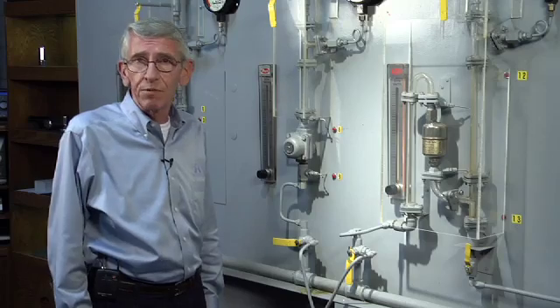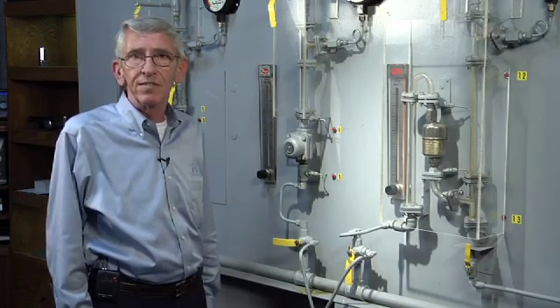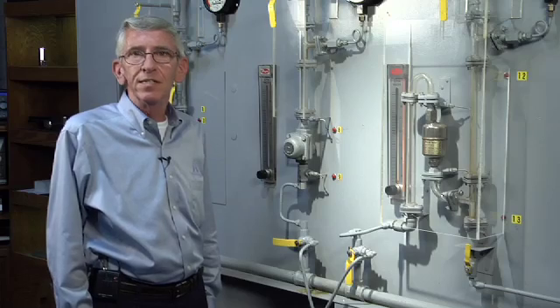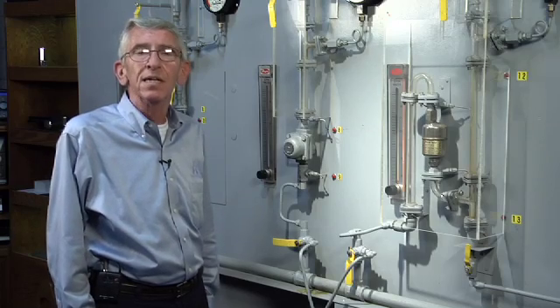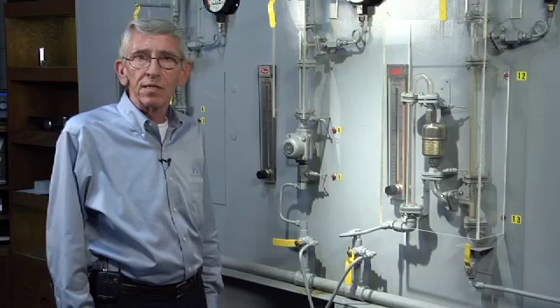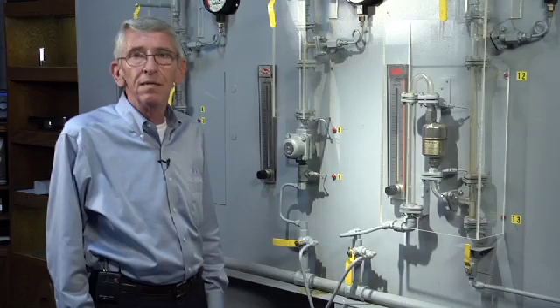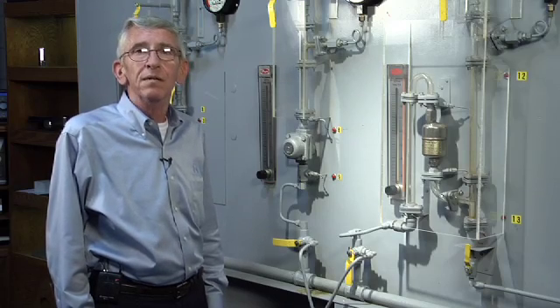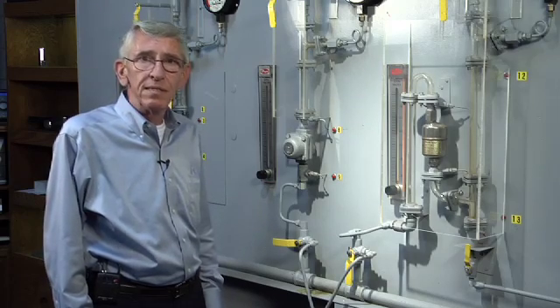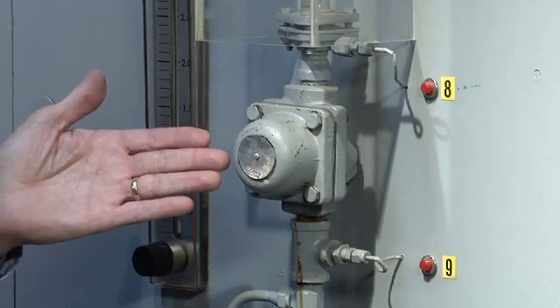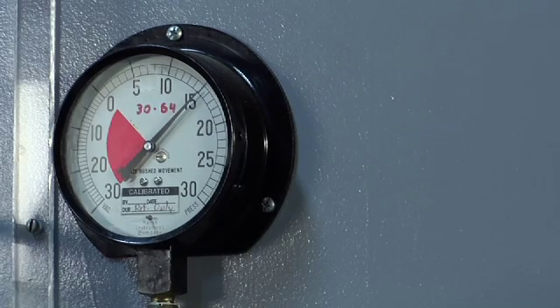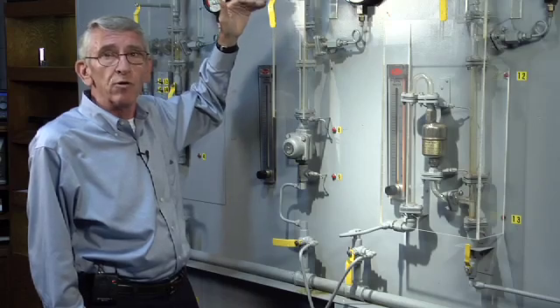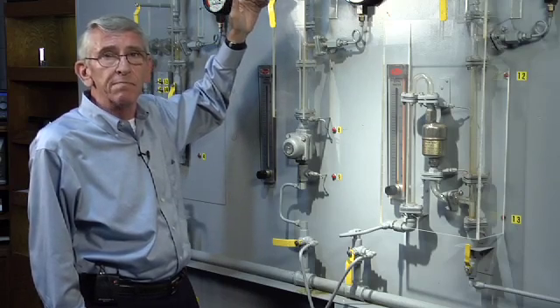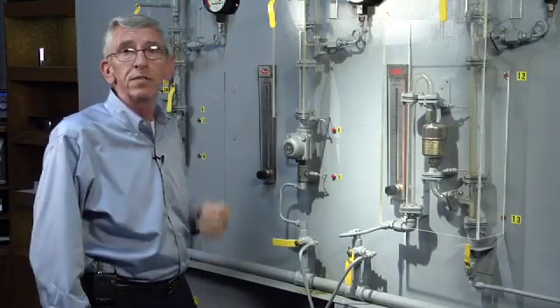The bimetal thermostatic trap operates on the difference in temperature between live steam and condensate. Since condensate is formed at or near steam temperature, for the thermostatic trap to work, we have to allow the condensate to collect long enough for it to lose heat energy and thereby lower its temperature, making the bimetal actuator operate. We're feeding these traps from 15 psi steam in the heat exchanger, and I can vary the load coming out of the heat exchanger by varying the amount of water that I run through the tubes.